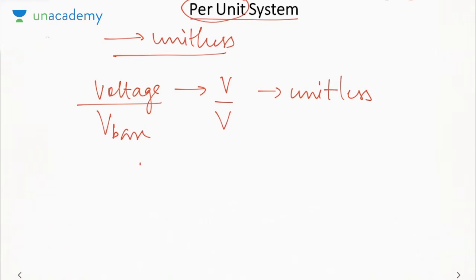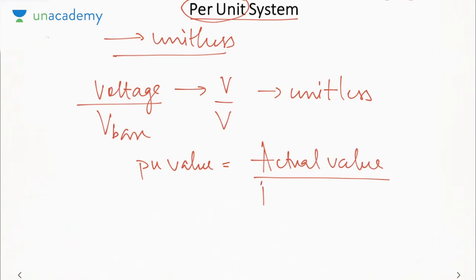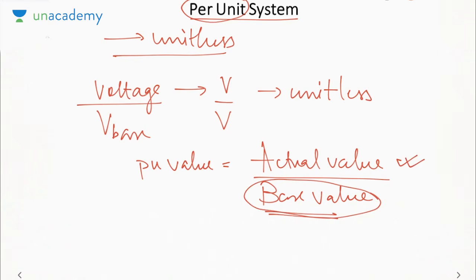Okay, so per unit value is actual value, whatever is given to you, divided by some standard reference, which is called the base value. So remember, per unit value depends on the choice of base, whatever is the standard that you are assuming or defining, whereas the actual value is independent of the base. Okay. And similarly, we can write the percentage value, which is equal to the PU value into 100.